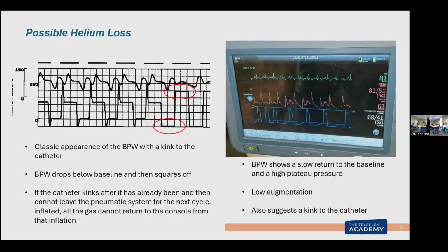Not the kink. If you have a minor helium leak, a microperforation, the pump can detect less than half a cc. So with a micro puncture, I might not even see blood in the tubing yet. The pump sent 40 out, expecting 40 back. It didn't get 40 back because it lost a little bit.